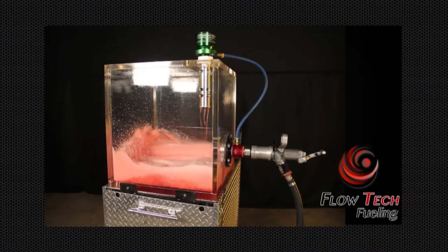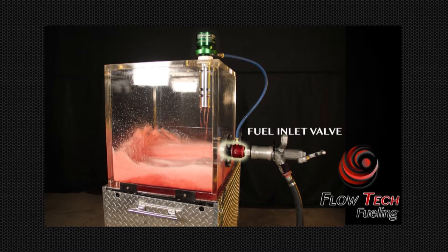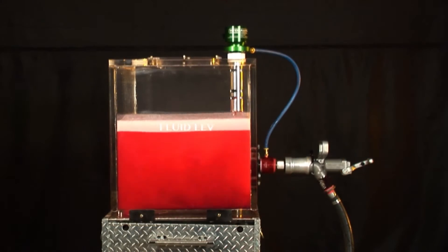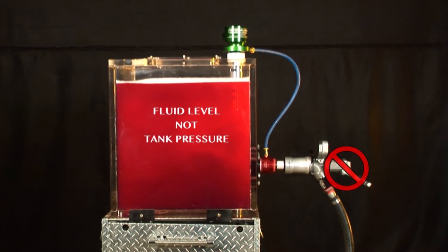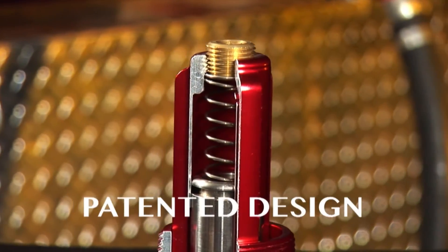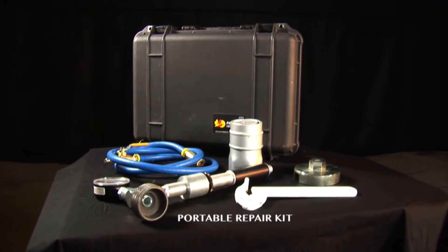The Hydroflow fueling system is comprised of a fuel inlet valve connected to a float control valve via a pilot hose. It is a non-pressure fueling system that provides a reliable, hydraulically operated fuel shutoff that depends on fluid level rather than tank pressure and cannot be manually overridden. The uniquely patented design makes it long-lasting and durable, yet simple to install, service, and use.